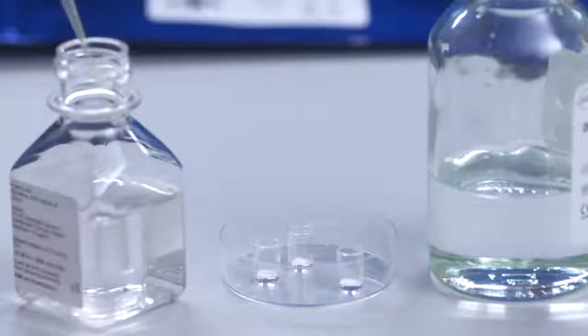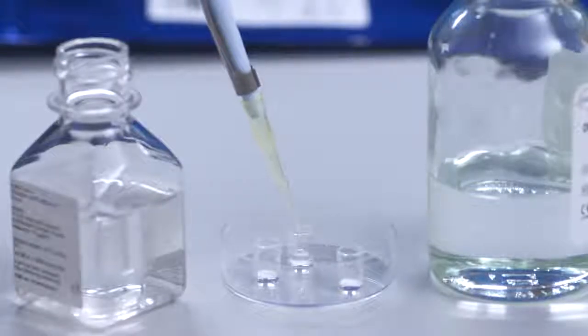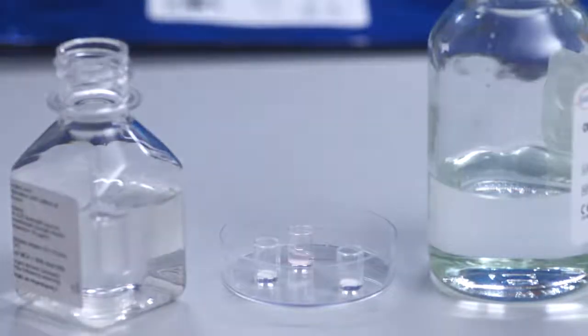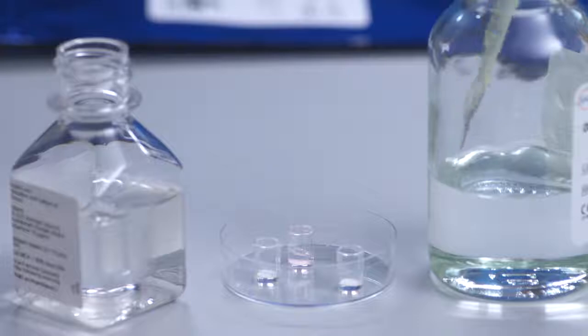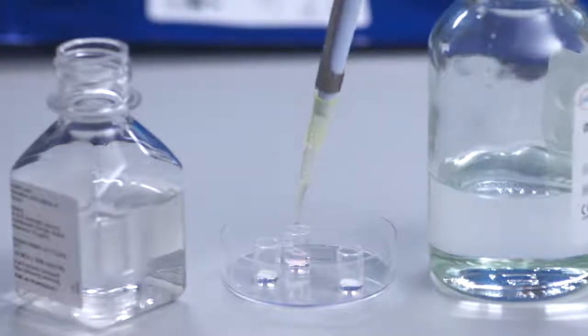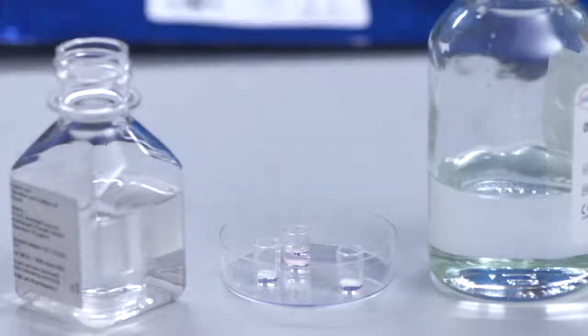After doing the site standardization protocol, you can use one of those sensors for a normal pH monitoring test. If you don't have a sensor available, prepare one with 100 microliters of media and 50 microliters of oil for humidified incubators and 150 microliters of oil for dry incubators. A new sensor should equilibrate overnight in the incubator before starting your pH test. A sensor from the site standardization protocol has already equilibrated and can be used immediately.